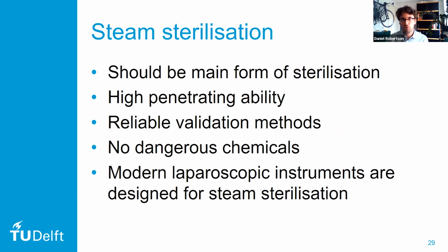Now, steam should be the main form of sterilization in your hospital. The advantage of steam is that it has a very high penetrating ability, which means that if there's a little residue still on the instruments, you can still rely that the steam will penetrate through small amounts of debris and sterilize the instrument. The other thing that makes steam reliable is that it has very reliable validation methods, which means that we can perform checks on the autoclaves to see whether the process that has been executed has been done safely. Steam also doesn't require any dangerous chemicals, so it doesn't provide any extra risk to your staff.